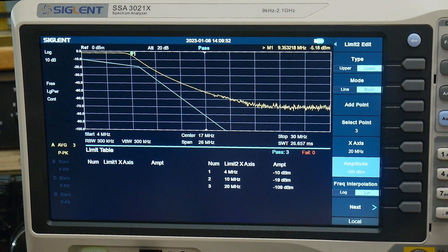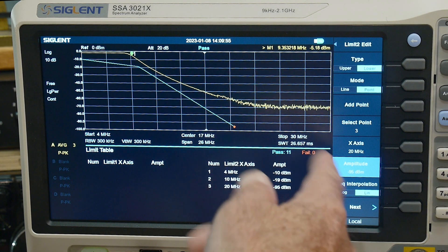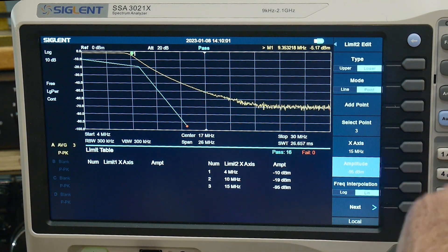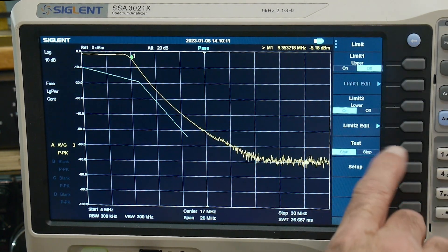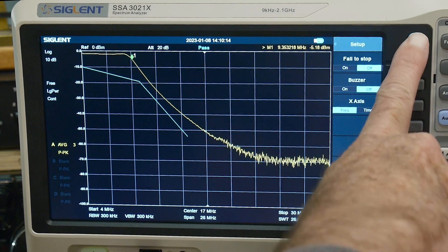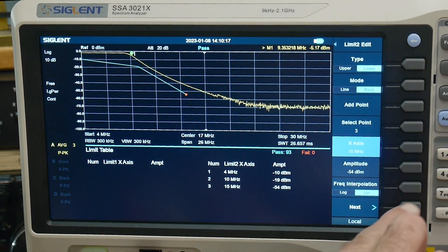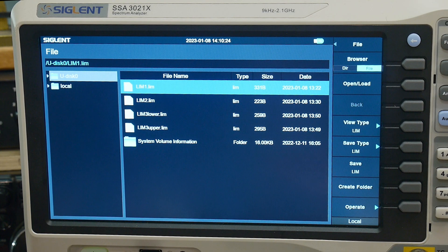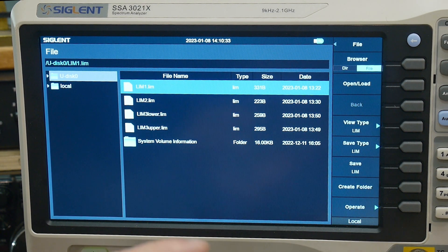If you mess up, you can go back and adjust — say, change 20 MHz to 15 MHz and then adjust the amplitude. Once you've created the limit line, to save: go to setup, edit limit two, then on the next page find save/load. Note that when you save, you're saving just the lower limit — you have to separately save the upper limit. You cannot save the upper and lower limits together into the same file.